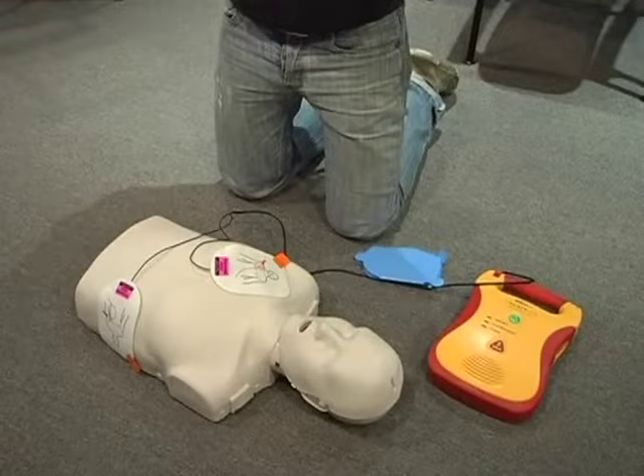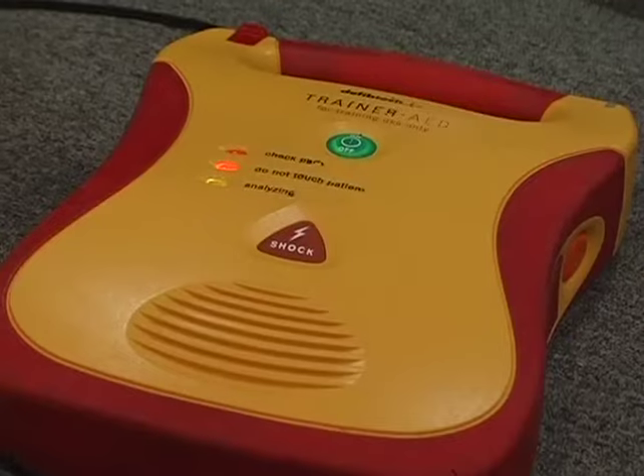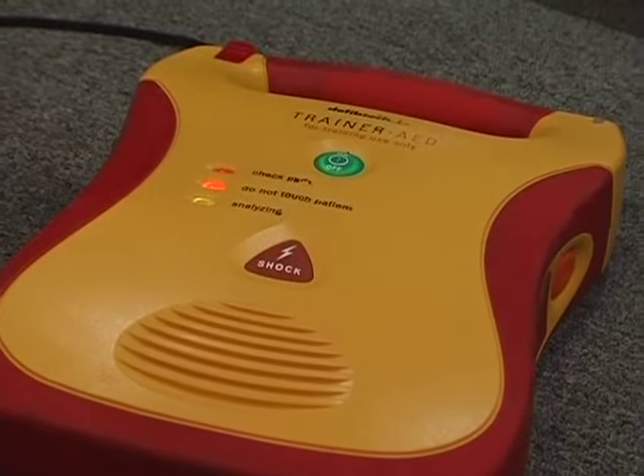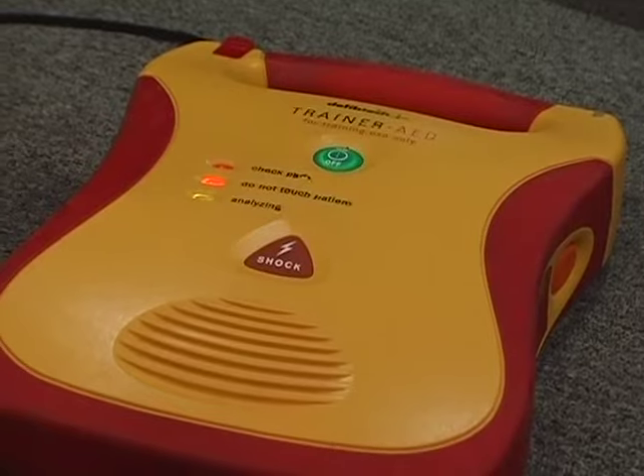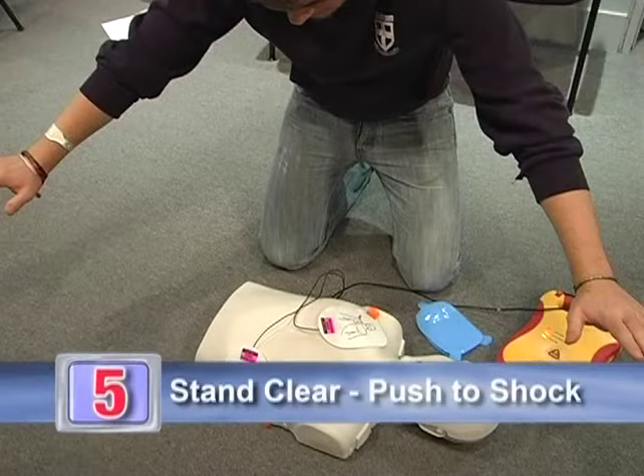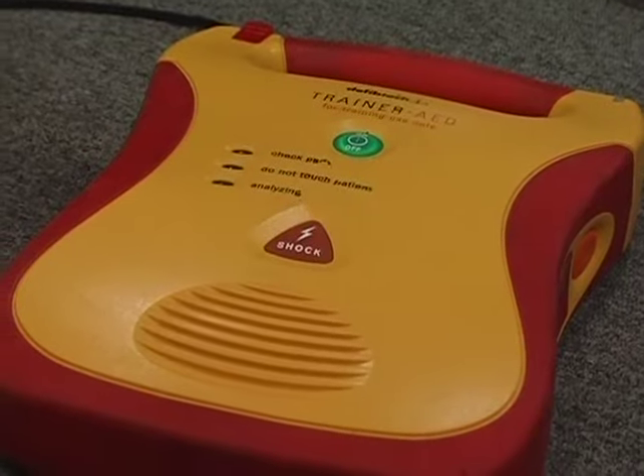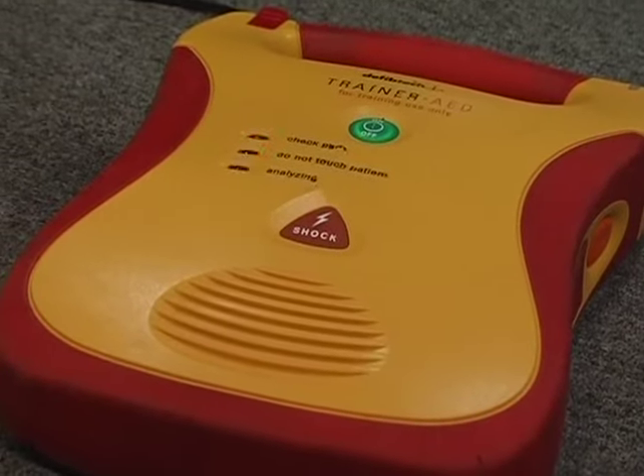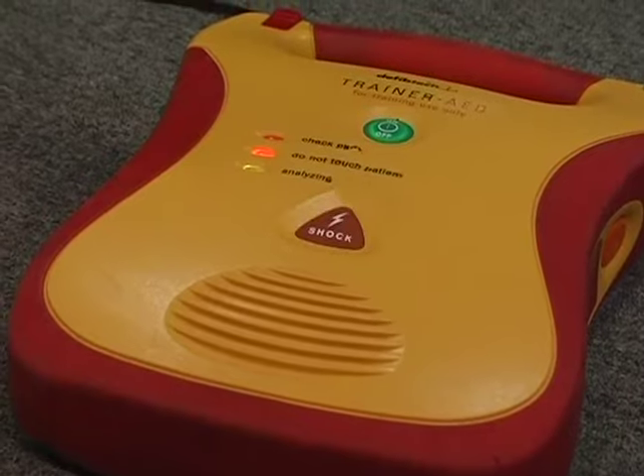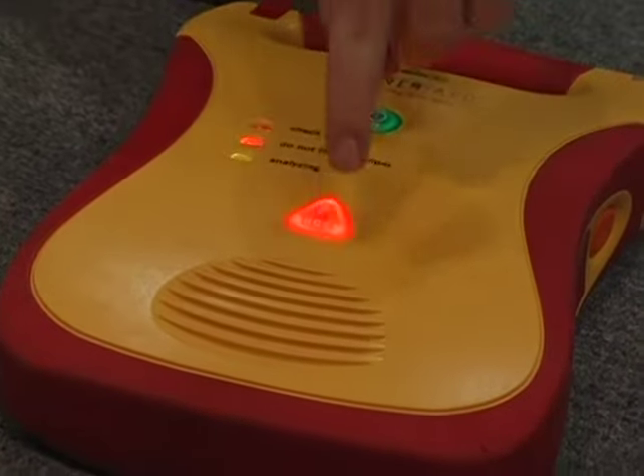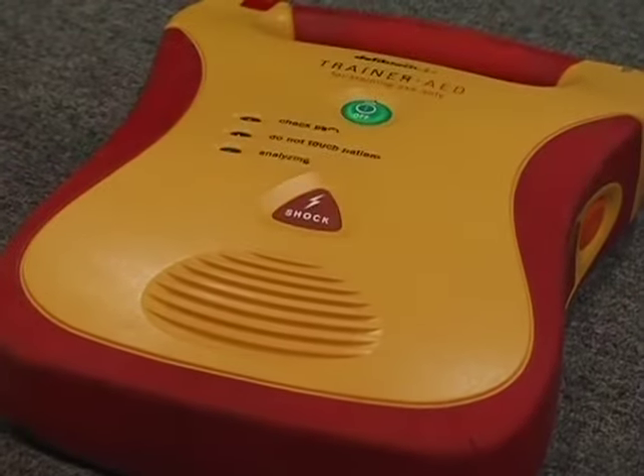If the AED advises a shock to be delivered, the user will be prompted, "Shock advised, charging." Shock advised, charging. When the unit is fully charged, the user is prompted to stand clear. Stand clear. An alarm will sound until the shock button is pushed. Press flashing shock button. Shock 1 delivered.